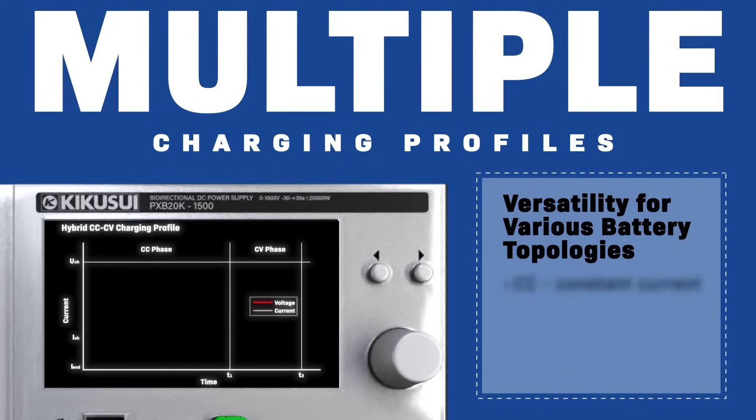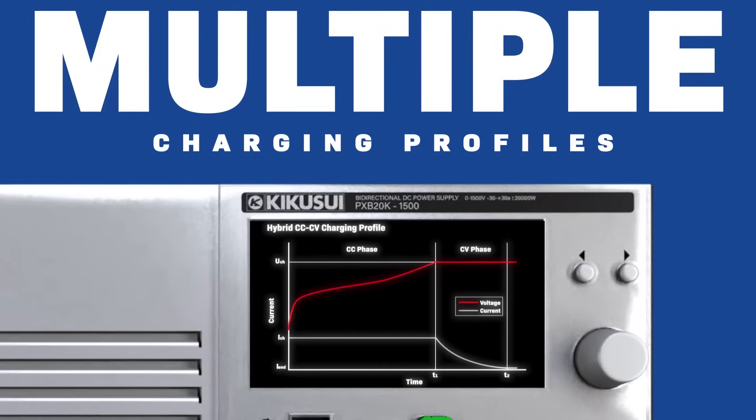The PXB accommodates different battery topologies with its multiple charging profiles including constant current, constant voltage, constant power, and hybrid CCCV. It supports steady-state behavior analysis and lifetime performance testing.